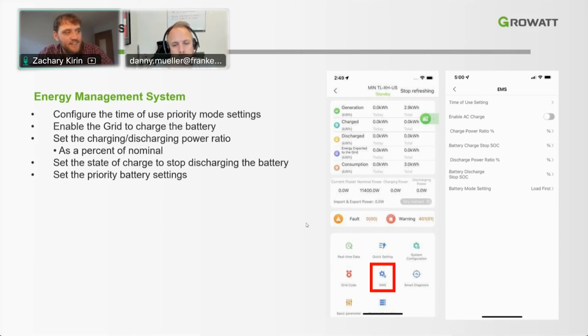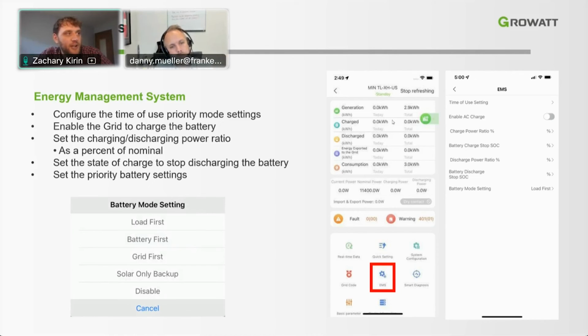We can set those battery settings here. Outside of the quick settings, it's in EMS. The first screen that you'll see when you click that is the time of use settings, enabling AC charge, charge power ratio percentage, and the battery charge and stop percentages, things of this nature. The time of use will be setting the various modes for the inverter to move in and out of. Say in a different application, we want to export some energy to the grid at certain times, or we only want to program grid charging of the battery at certain times. We can do so within the time of use setting.